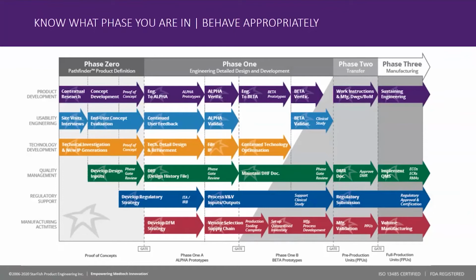There's a freeze of the design, and then it goes through the final formal verification and validation, which can include clinical testing. And at the end of that, there's an approved design, which if it changes, has to be changed under control, engineering change control, and if there are issues that would affect the previous verification and validation, then that testing needs to be repeated. So we want to be pretty firmly finished before we go into that verification and validation process.